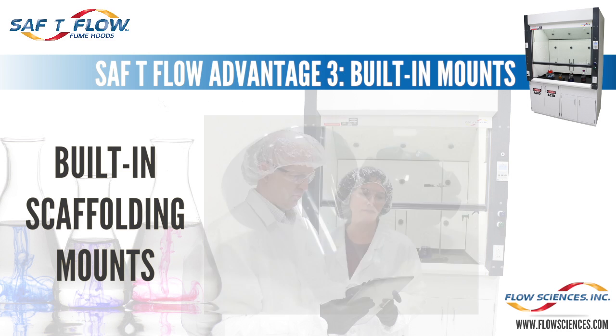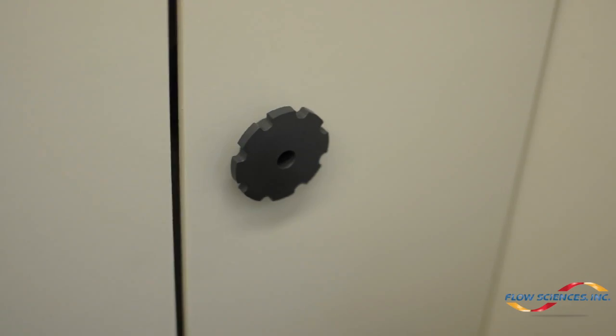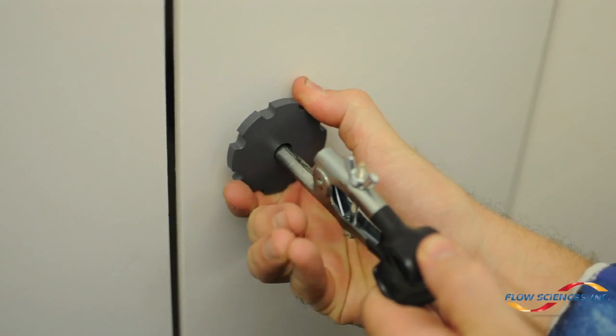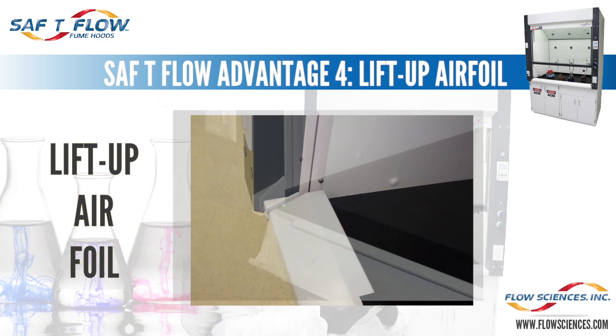Advantage three: every Saf-T-Flow fume hood is constructed with the hardware to hold scaffolding built into the baffle knobs. The plastic mounting knob doubles for holding the mounting dowels for the scaffolding. This is a huge advantage in time and convenience, because any hood you purchase can immediately accept the scaffolding. Advantage four: the Saf-T-Flow fume hood has a lift-up airfoil. This special airfoil allows easy cleaning and easy cord routing through the hood front to the exterior outlets.